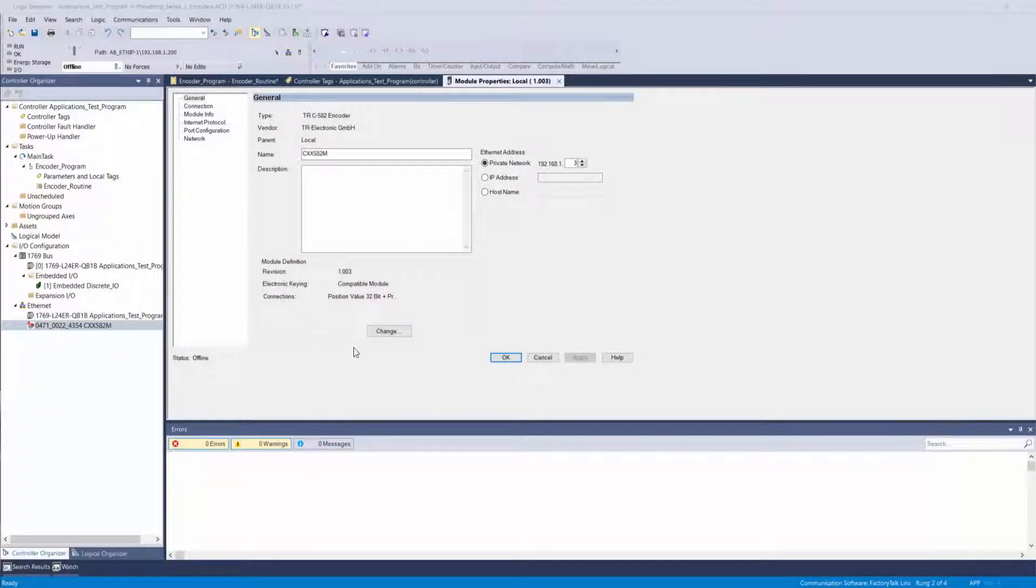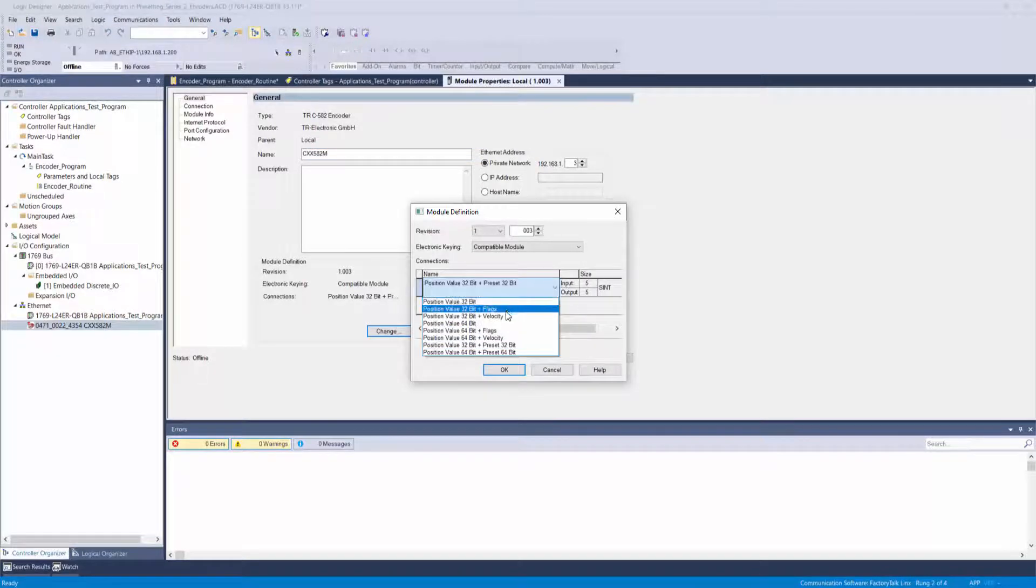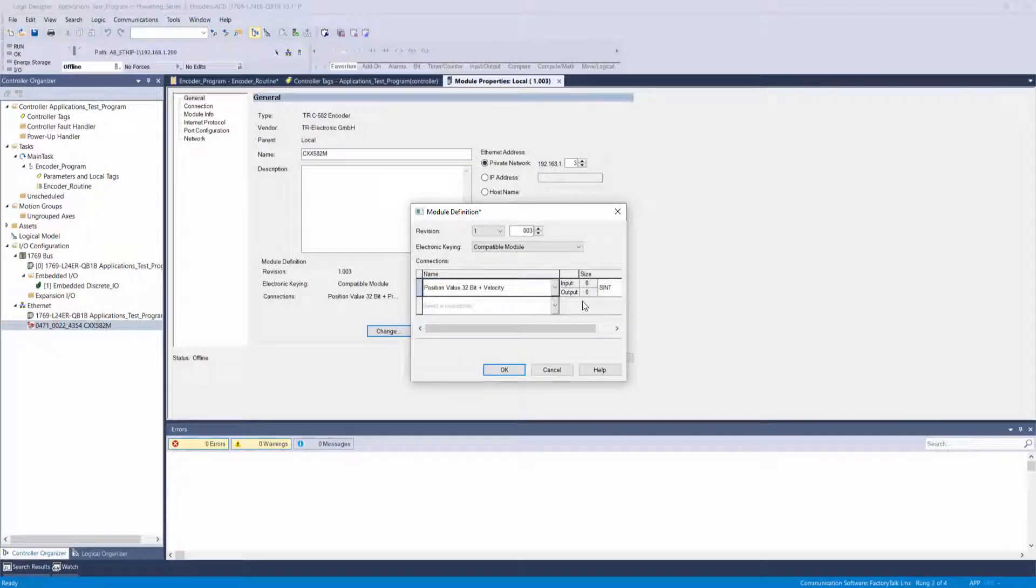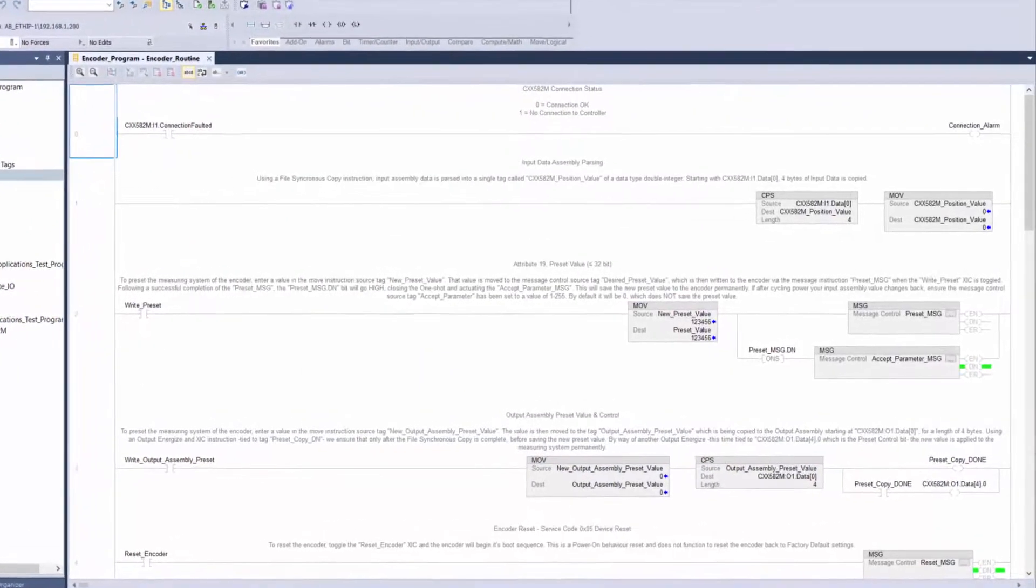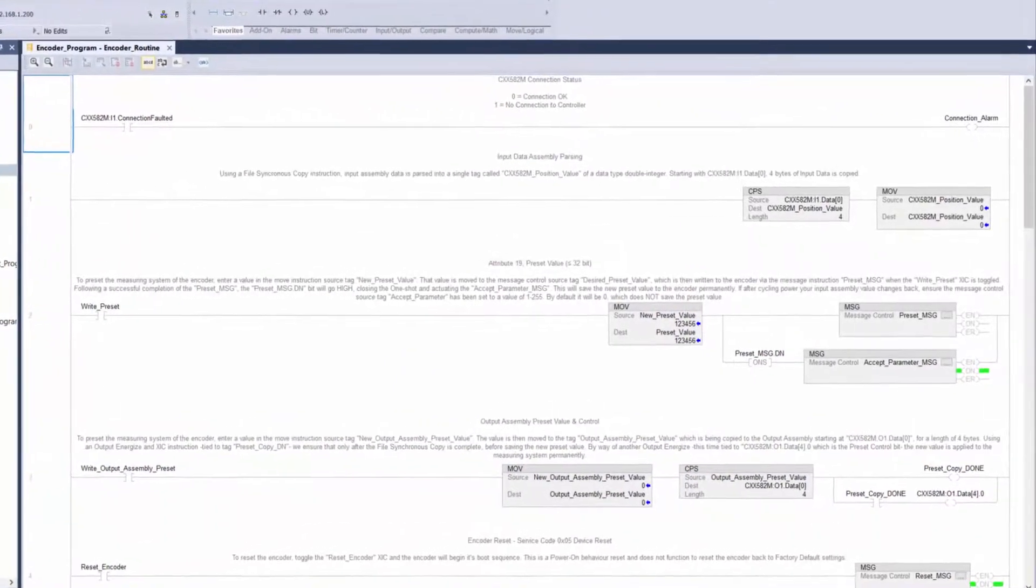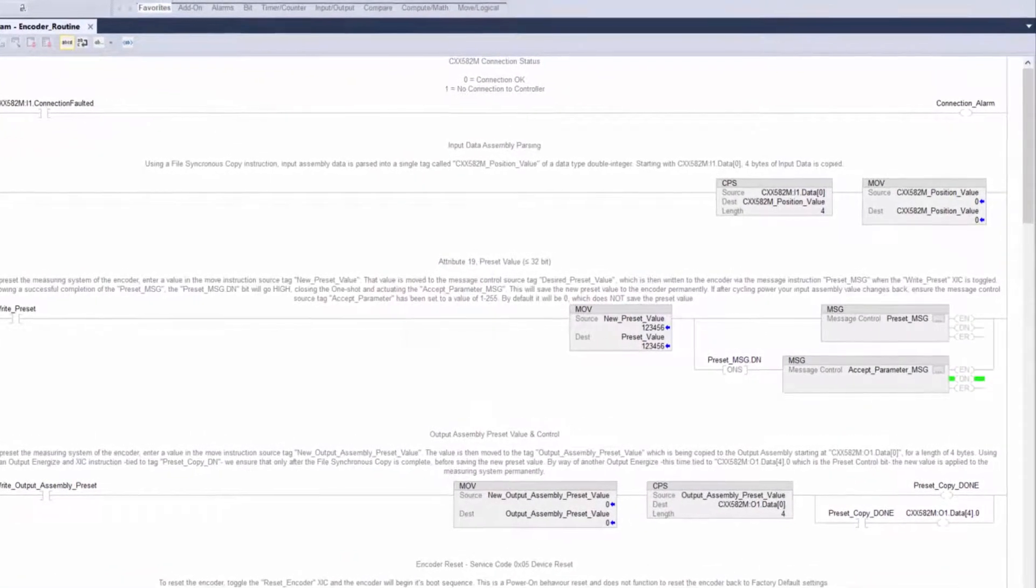This was pretty simple to do, but in the case that you want to use position and velocity data in your input assembly, you can see that the output assembly data is no longer available. In this case, you need to preset the encoder using class 3 explicit message instructions.